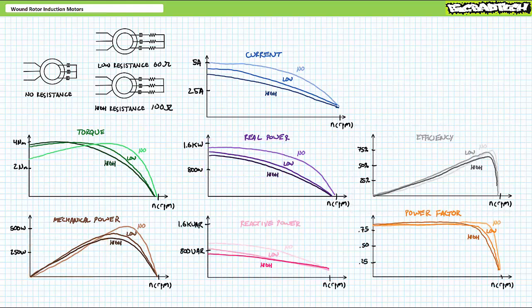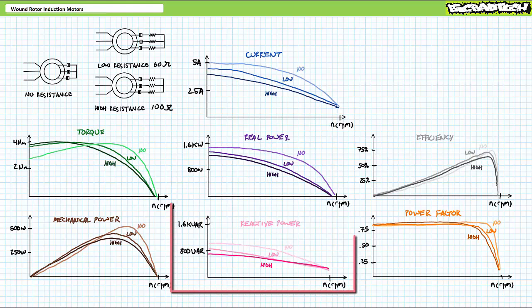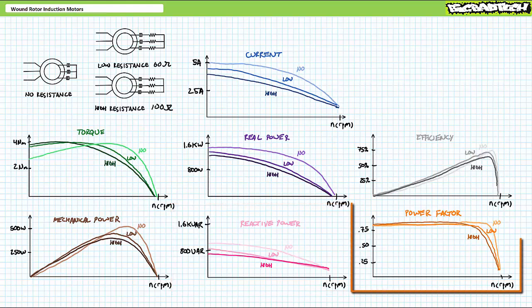Let's take a look at reactive power and power factor for these three configurations. Given each motor operates using the principle of induction, there's a draw of positive reactive power even in the low load condition, which gradually increases and eventually flatlines. Each configuration exhibits low power factor at no load conditions, since a significant portion of apparent power is directed towards reactive power. As each configuration moves towards the rated condition and beyond, a larger portion of apparent power is directed towards real power and less towards reactive, such that power factor increases. Inside the breakdown region, the ratio of real and reactive power remains relatively constant and power factor flatlines.